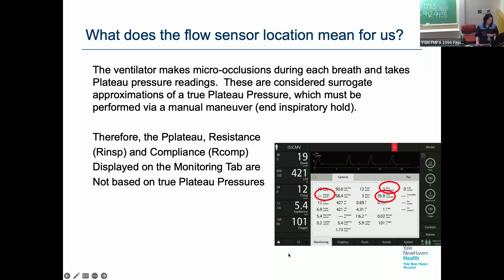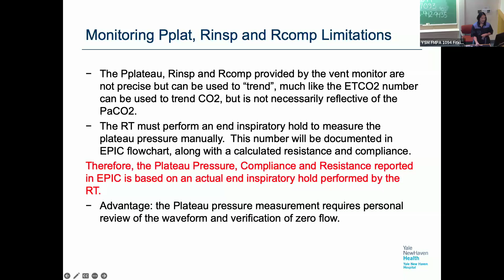The advantage of this is that prior to the Hamiltons, when we had the Avias, you used to see plateau pressures being measured, and due to the workflow of the respiratory therapist, sometimes that plateau pressure didn't make sense. Sometimes the patient was inspiring during the plateau hold, and you just knew intuitively that it was not valid. Well, here, every plateau pressure that's measured, the RT is made to look at the waveform, made to assure that there's zero flow occurring when they're measuring the plateau pressure. So I'm really happy about that.